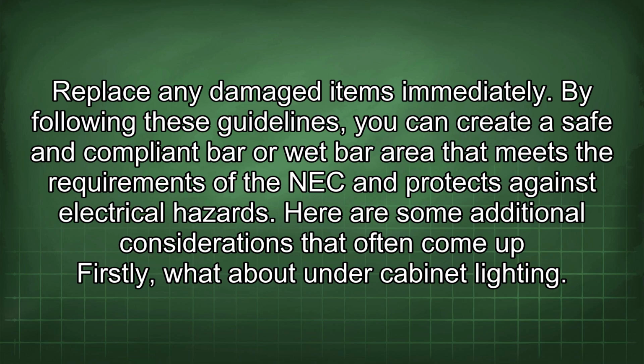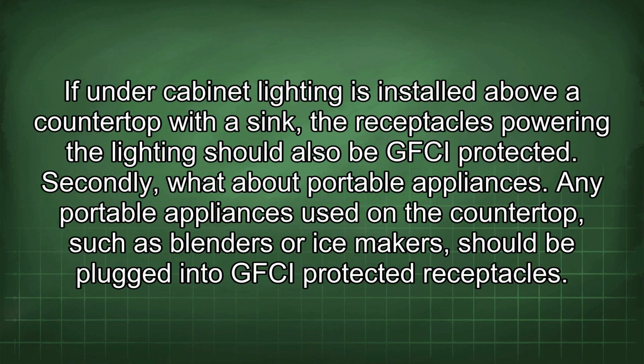Here are some additional considerations that often come up. Firstly, what about under cabinet lighting? If under cabinet lighting is installed above a countertop with a sink, the receptacles powering the lighting should also be GFCI protected. Secondly, what about portable appliances? Any portable appliances used on the countertop, such as blenders or ice makers, should be plugged into GFCI protected receptacles.